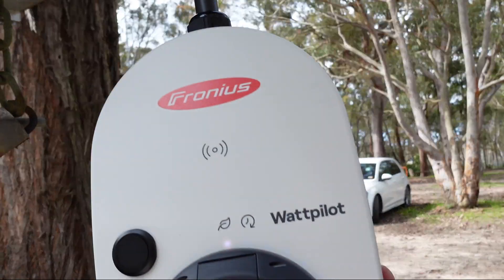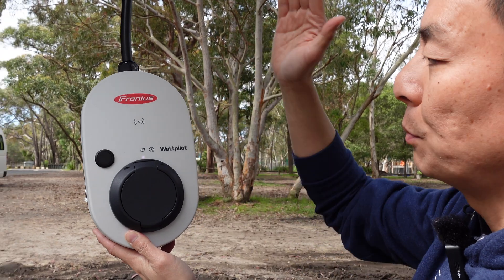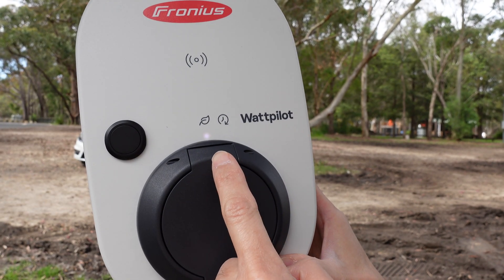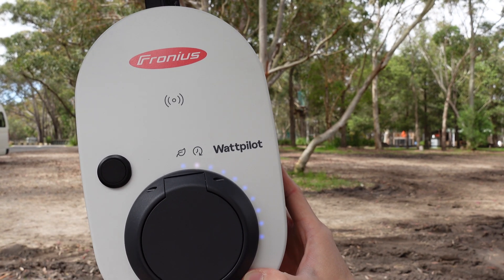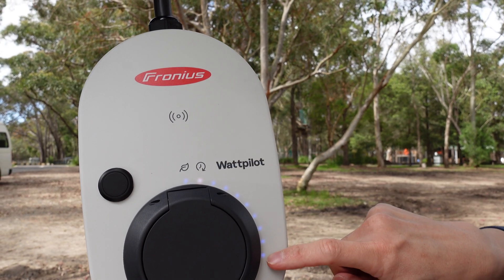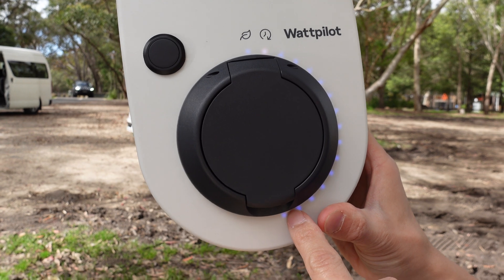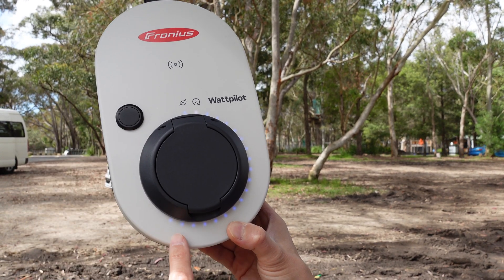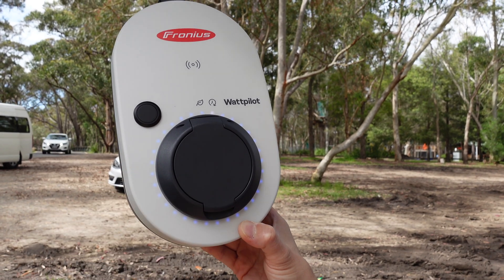Looking at the unit, you'll see lights flashing initially, then a steady blue light — that's what we want. When plugged in and set up correctly, there's a white light you can toggle with the button. The first white light is eco mode, using excess solar from your Fronius inverter; the next is Next Trip mode, charging at maximum available from the grid. Ten blue lights indicates 10 amps. Hold the black button for two seconds to go to 16, keep pressing for 20, then 24, and one more press gives you the full 32 amps.